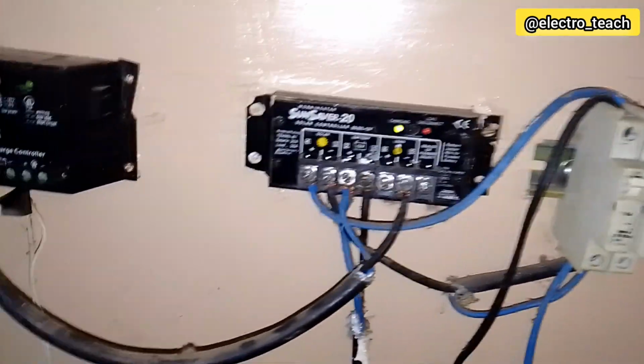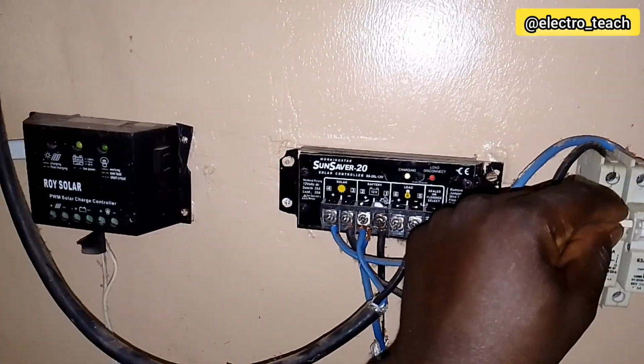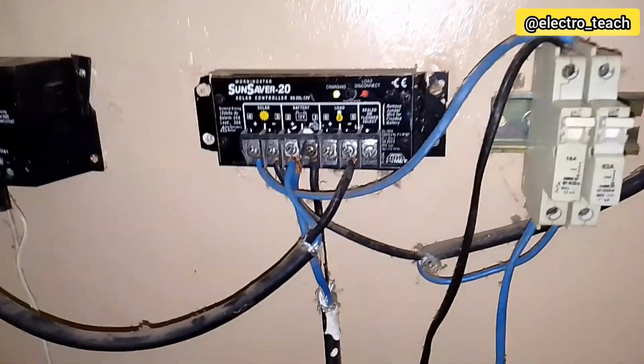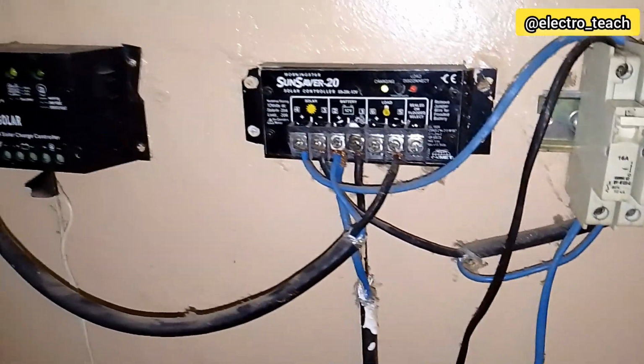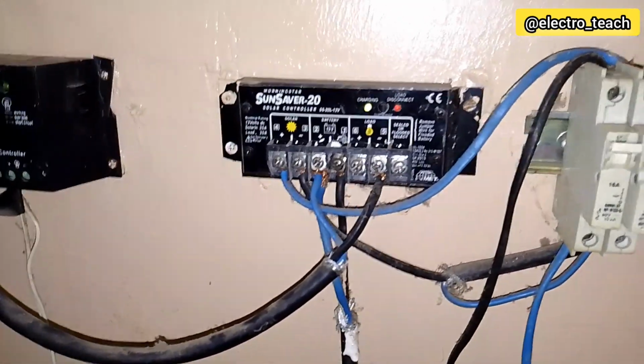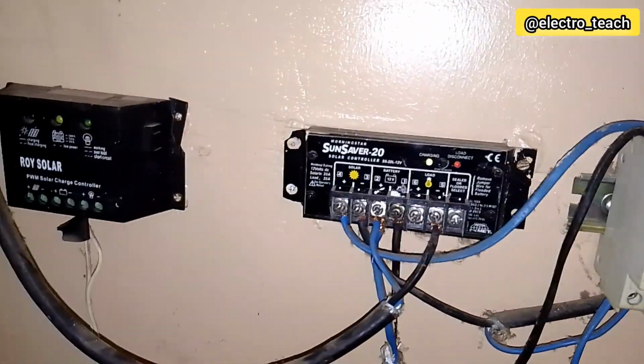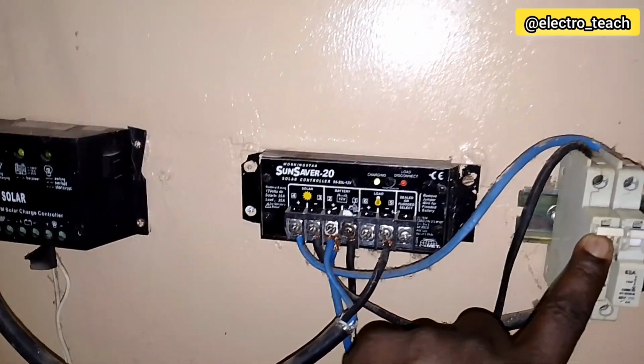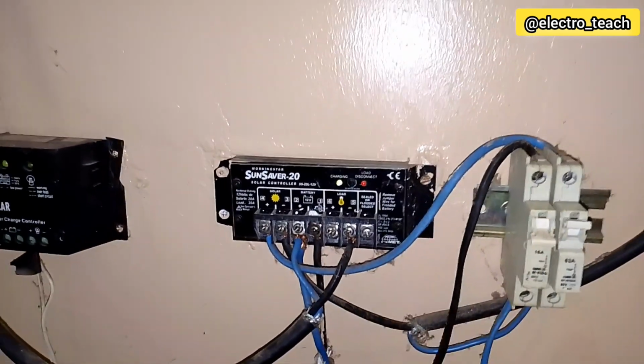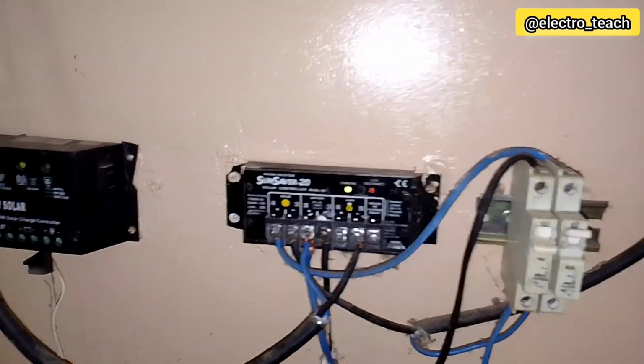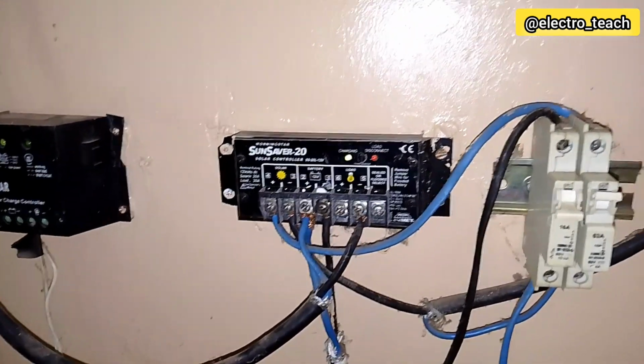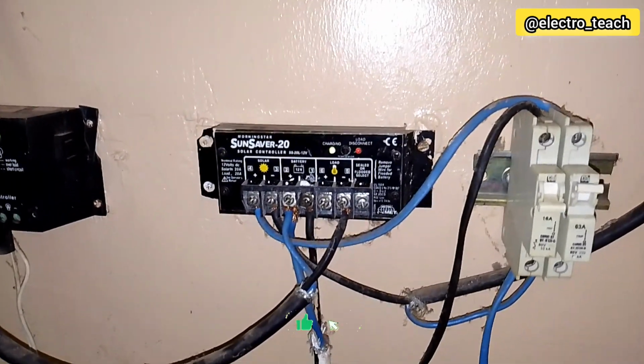The second protection part is this circuit breaker. When there is anything wrong with the battery, whether there is a wrong connection that results in sudden high current, this second circuit breaker will trip off like this. Once that happens, power will not reach the inverter, so the inverter will not get damaged.